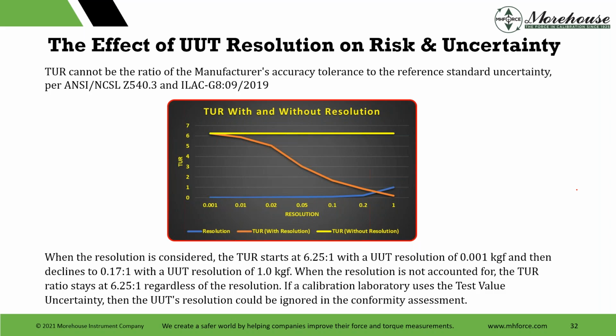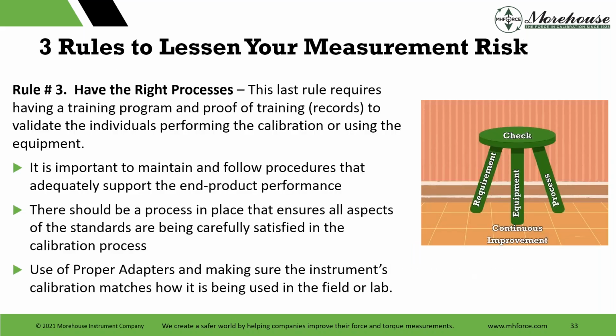And if a calibration laboratory uses this other test value uncertainty instead of test uncertainty ratio, then the UUT resolution can be ignored for conformity assessment, which you can make the decision whether that's right or wrong. I think I've painted the case on why it is wrong. And one other thing is if I make a measurement and you make a measurement of one device, say it's a micrometer, the only thing that may distinguish us is the resolution of that device, if we're both trained technicians.